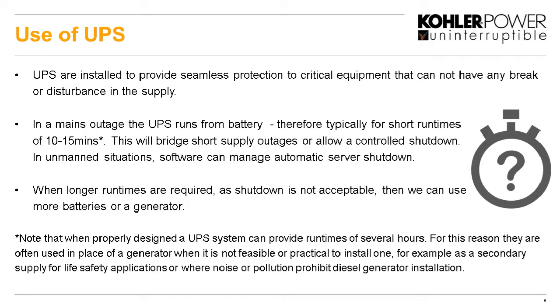In situations where it's unmanned, that shutdown can be automatic and managed by shutdown software controlled from the UPS. Now, when we want longer run times and shutdown is not acceptable, we can use more batteries, or very typically a generator, to make sure we can run for as long as required. We can have UPSs with several hours of batteries, but that is only typically where it's not practical or feasible to fit a generator. If we have a UPS with several hours of batteries, we have to be very careful that the UPS is designed correctly to be able to charge and look after that battery for those several hours.